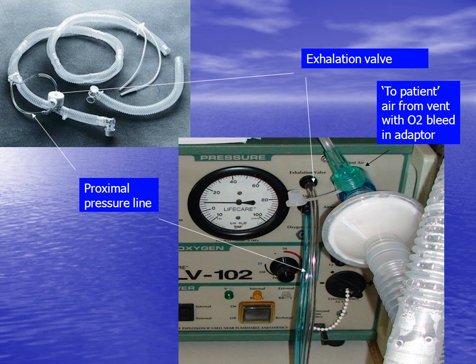The circuit utilized by this vent requires a proximal pressure line to monitor patient pressures, as well as a second pressurized line which activates the exhalation valve on the circuit. The activation of this exhalation valve is how the vent regulates when it will cycle from inhalation to exhalation. This illustration also displays a filter placed at the to patient port, as well as the addition of oxygen into the circuit or bleed-in O2.